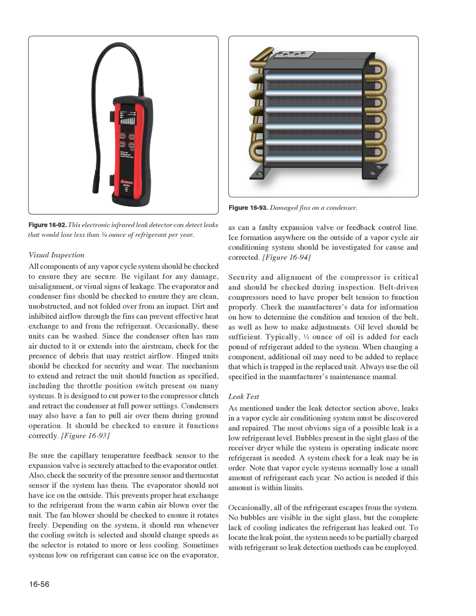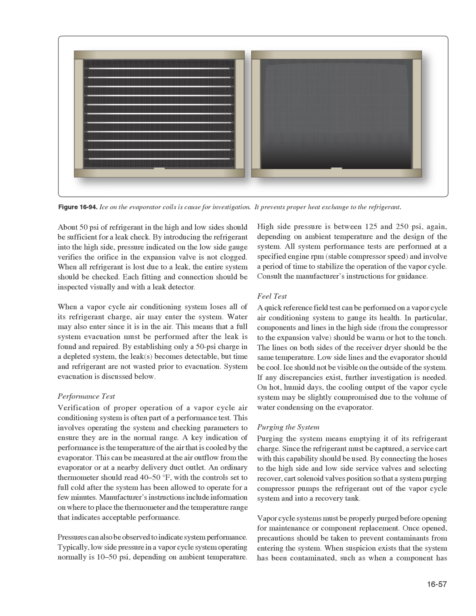To locate the leak point, the system needs to be partially charged with refrigerant so leak detection methods can be employed. About 50 pounds per square inch of refrigerant in the high and low sides should be sufficient for a leak check. By introducing the refrigerant into the high side, pressure indicated on the low side gauge verifies the orifice in the expansion valve is not clogged. When all refrigerant is lost due to a leak, the entire system should be checked. Each fitting and connection should be inspected visually and with a leak detector.